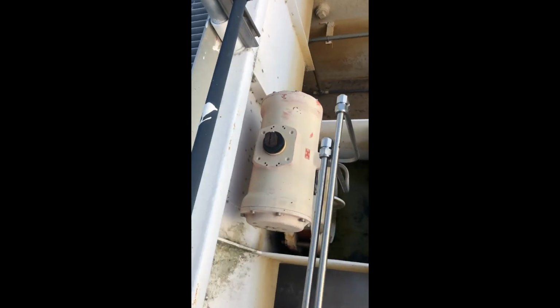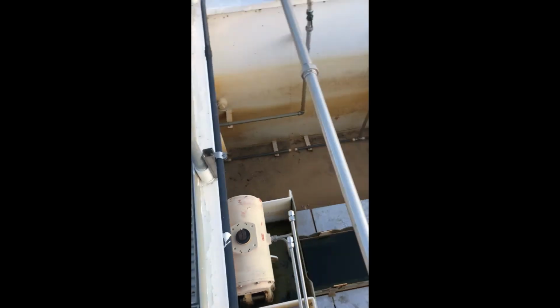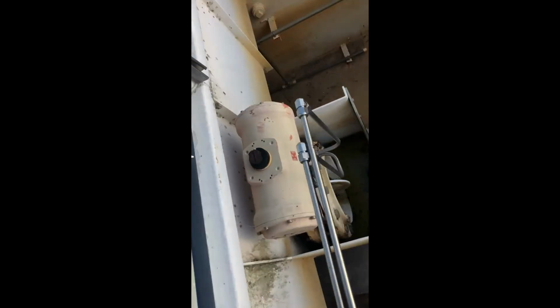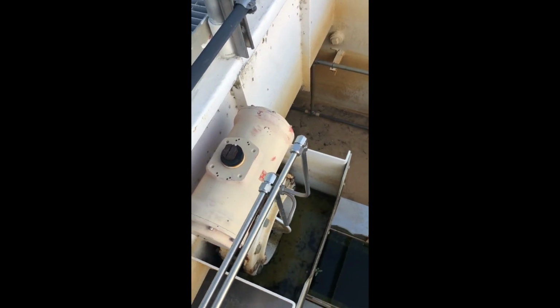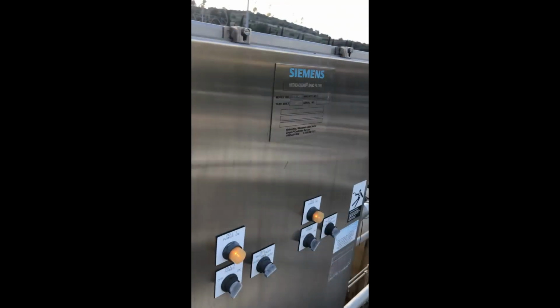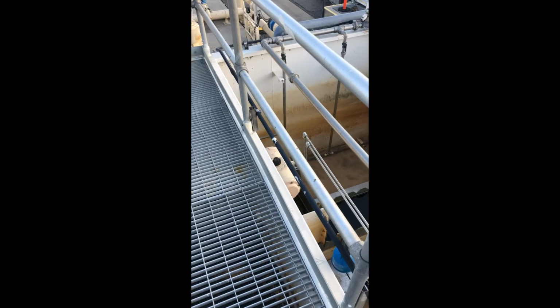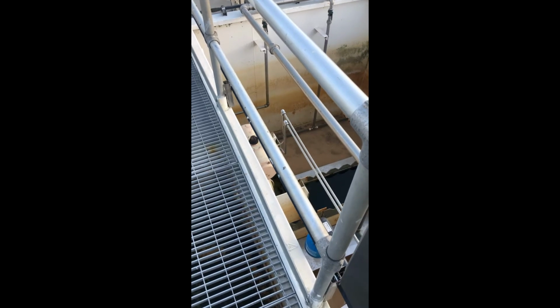This is the control panel, and I wanted to point out these. This valve here is the fill valve. This is where the water comes from this center channel and goes into the filter. It is pneumatically controlled. That's the pneumatic actuator there. You have the 2 air lines. The 2 air lines are going up into here, and then up inside the panel we have a couple of pneumatic solenoids that open and close with that air directional valve. We give it 120 volts and it shifts the spool over, directs air to the different sides of this pneumatic actuator, and opens and closes that feed valve.